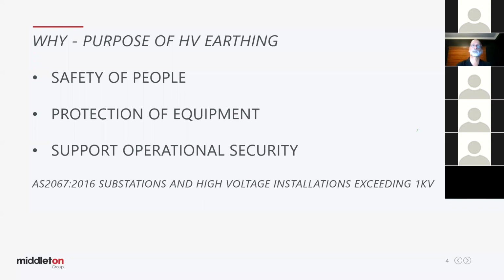But earthing is also there for support of operational security. So on our electrical grid, we do expect the voltage to be within a certain tolerance and, of course, the frequency to be at 50 hertz. If we experience a large earth fault in part of the grid, obviously the voltage for that phase will be dragged towards zero. But when we lose that big load, if it's a huge load, a big industrial load, that'll affect the frequency as well. The frequency will go higher, losing the load off the grid, as you probably know. So the purpose of earthing is threefold: safety of the people, protection of the equipment, and also operational security.